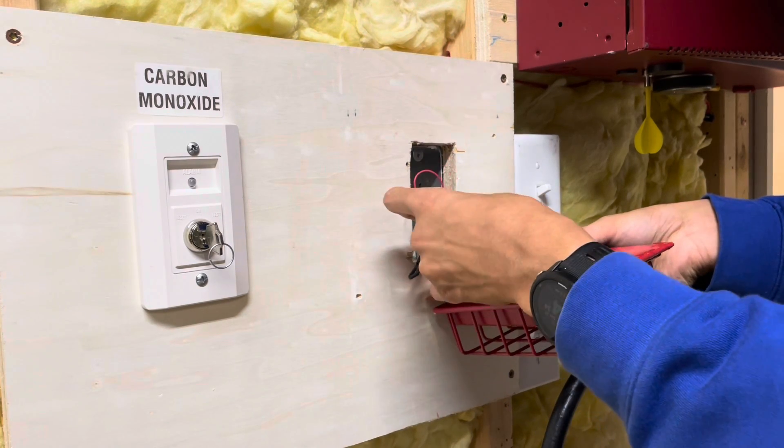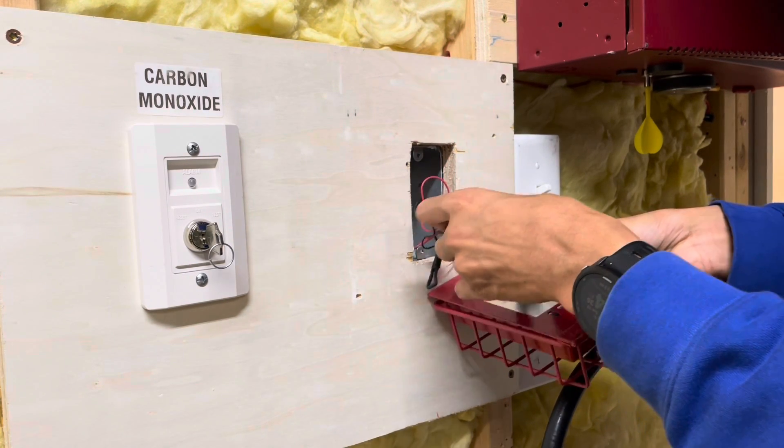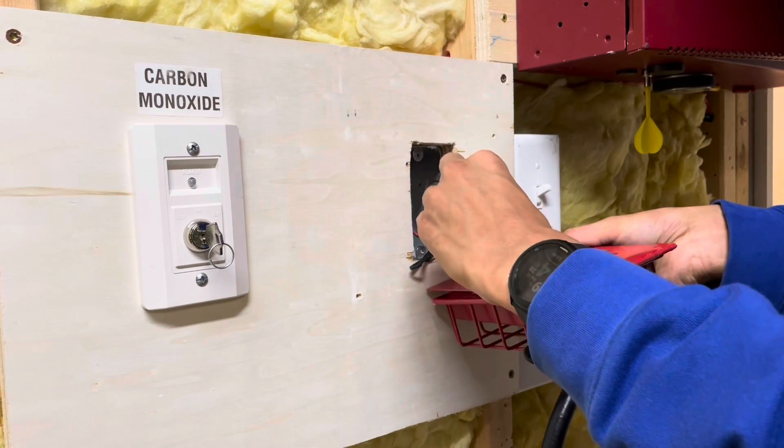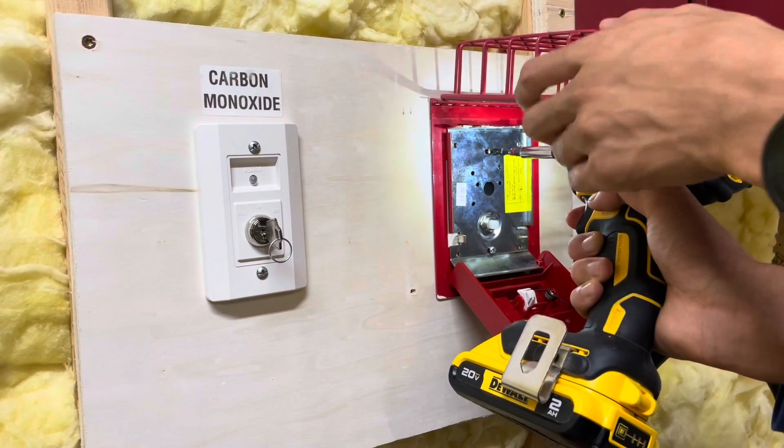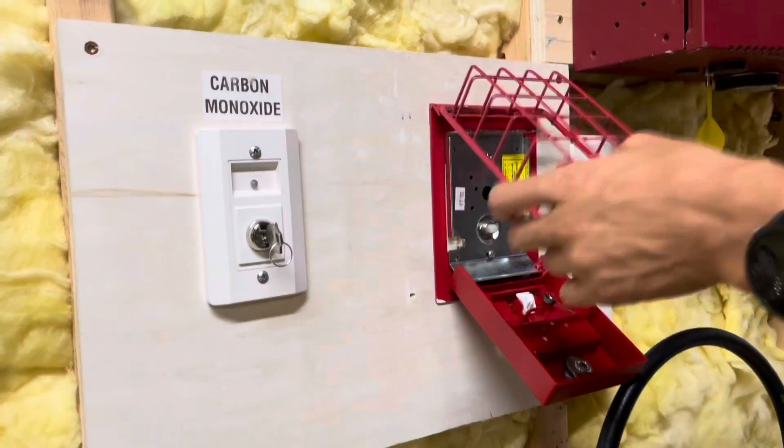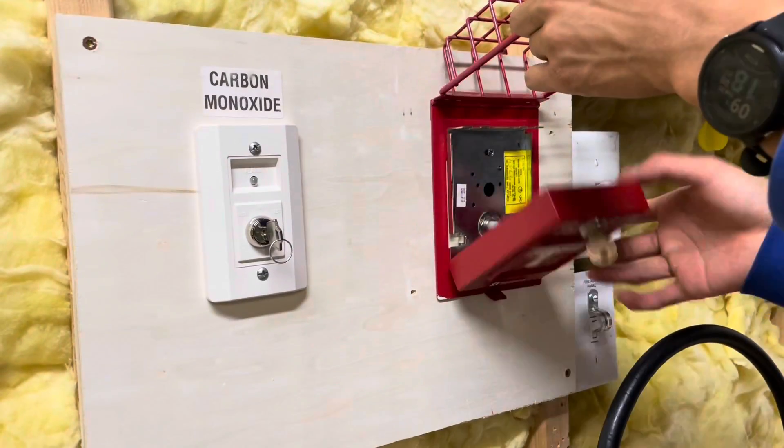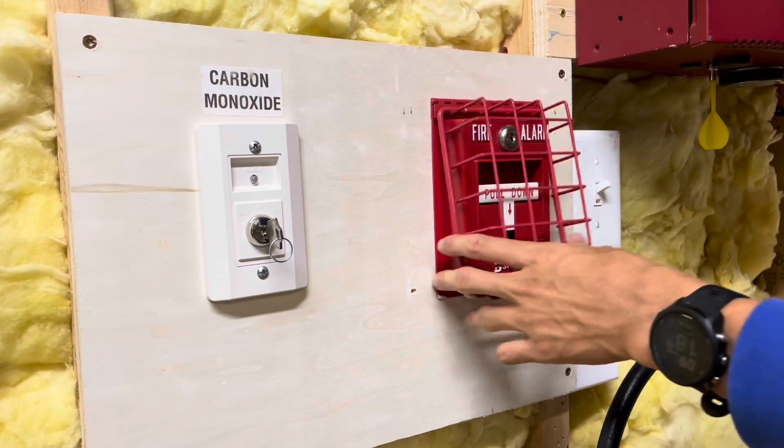Put one lead of the end of line resistor in as well because this is the last device on the circuit. It's pretty simple I guess. You're just sending the screws through the cage. To do that you can close the station and shut the cage.